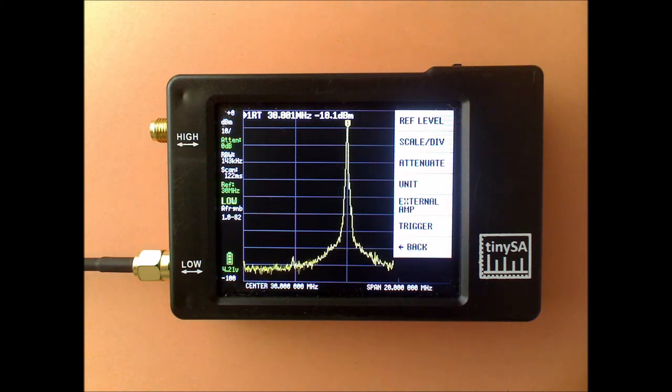The REF level is normally set automatic to ensure that the strongest signal is just visible and if there is no strong signal that the noise is at the bottom of the screen.